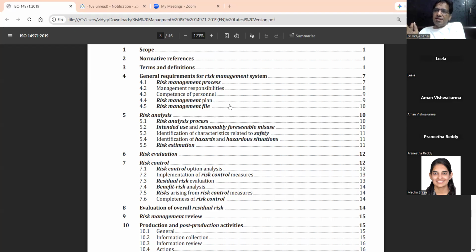Okay. Then after understanding or correlating this residual risk versus the events that are happening in the clinical scenario, how you convey this to the end user is in the form of the IFU. In the IFU you don't write your residual risk, but you write that these events could happen. I've seen a lot of IFUs where they write even that some deaths could happen. Like 10-15 years back when I wrote an IFU, because the clinical evaluation reports, even the clinical data, showed that there could be 1% death, and we needed to mention it in the IFU, like 1 out of every 100 patients is going to die.